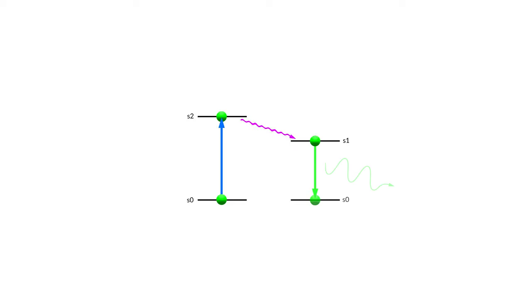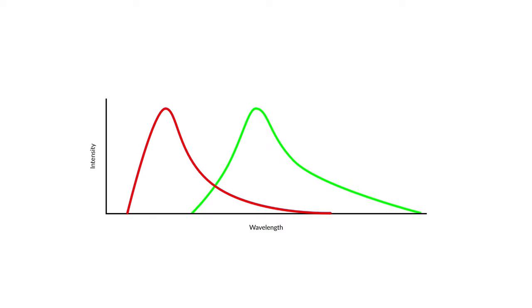Excess energy is released as an emission photon. All fluorophores have an ideal range of wavelengths that will excite them, as well as a range of wavelengths where the fluorophore nominally emits its emission light. It's important to understand the particular excitation and emission profiles of the individual fluorophores you want to use for your experiments. This information will be critical to configuring your microscope's filtering system.